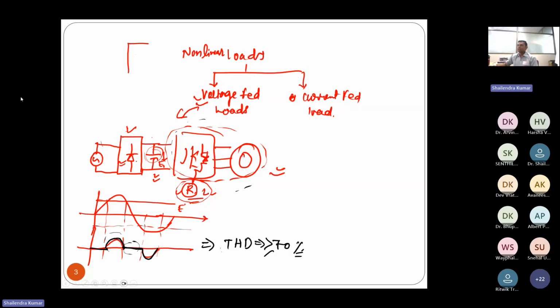And the moment you put this, you will pollute the power grid because of total harmonic distortion. Again, they have provided some standard for power quality as well. What is the power quality standard? We have IEEE 519, which says THD must be less than 5%. And here you are polluting the grid and the THD is more than 70%.